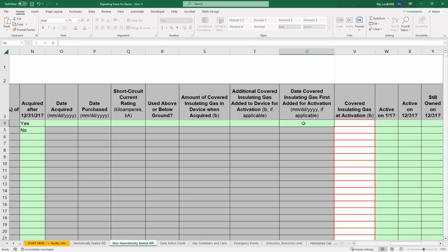That brings us to column V, covered insulating gas at activation, or CIGA. For GIE acquired and made active after December 31st of 2021, this value is the amount of gas inside the device when acquired, plus the additional amount of gas added for activation. For all other GIE, CIGA is the nameplate capacity. Following these rules, the form will automatically calculate CIGA for you.